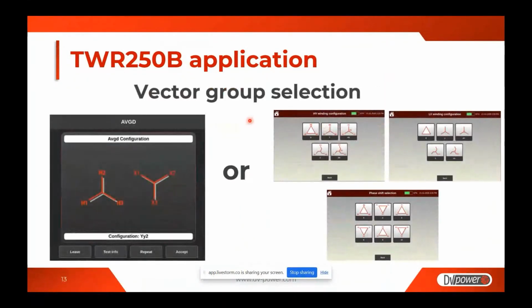Regarding vector group detection, as already explained, it's possible to automatically perform the test or select the vector group manually. Here you can see the steps. So firstly, you select high voltage winding configuration, then low voltage winding configuration, and phase shift selection is also possible. And if you do not want to perform that, you can perform automatic vector group detection, which will be shown during demonstration. The device can automatically select the vector group.